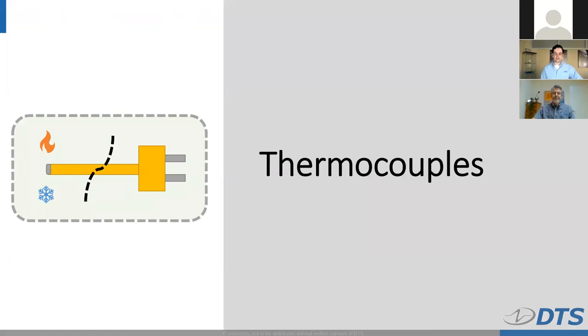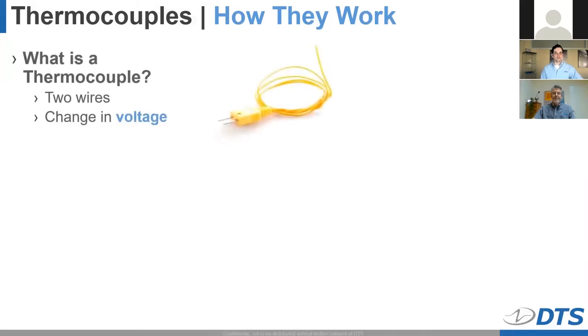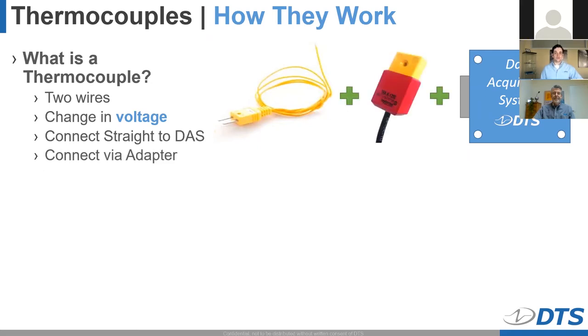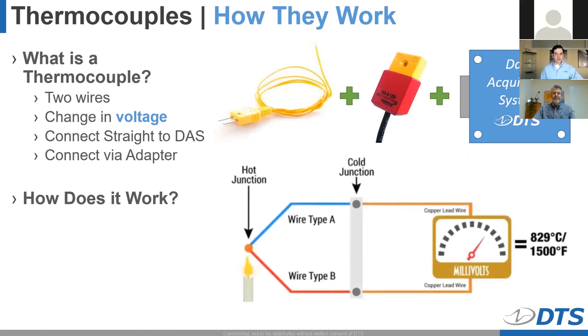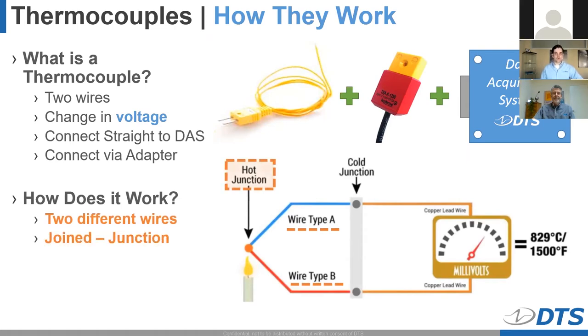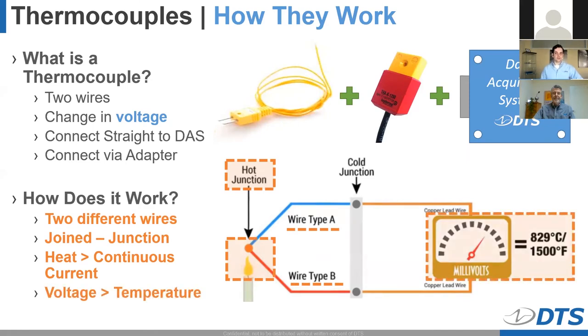Next, the reigning champion from our polls: thermocouples. How do these work? These measure the change in voltage as the temperature changes — another common, simple solution. You can either connect them directly to your DAS or use an adapter. Simply put, two wires of differing material are joined at one end — this is called a junction, or a hot junction, which is where the temperature itself is measured. As this is heated, it creates a continuous current, and the resulting voltage can be read as a temperature.